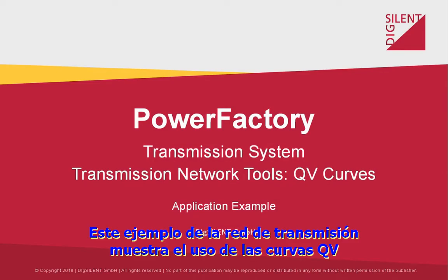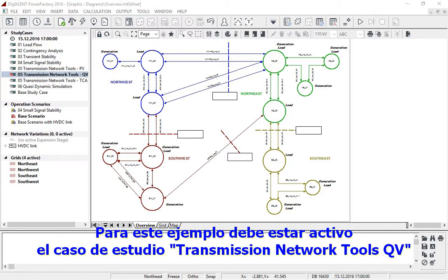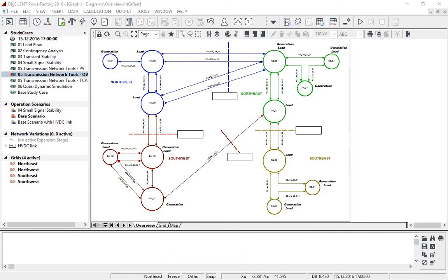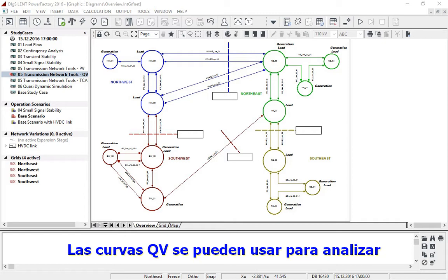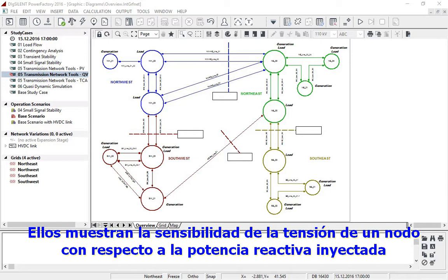This transmission network model example demonstrates the use of QV curves. QV curves is one of the options available in transmission network tools. For this example, study case transmission network tools QV and scenario base scenario should be active. QV curves can be used when analyzing the voltage stability of a network. They show the sensitivity of the voltage of a node with respect to injected reactive power.